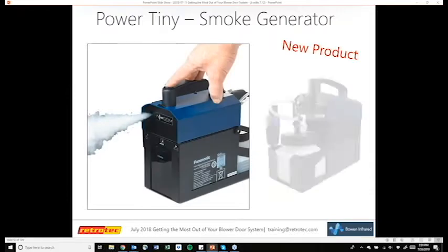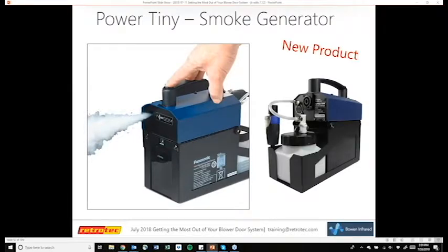And so the Tiny S has a big brother called the Power Tiny. So this is a bigger fog machine that you can actually use to fill up a room or sometimes a whole house, and definitely a duct system. And that way you can either step outside and see where the leaks are coming from, or you can run your blower door and follow the smoke inside to see where it's escaping.